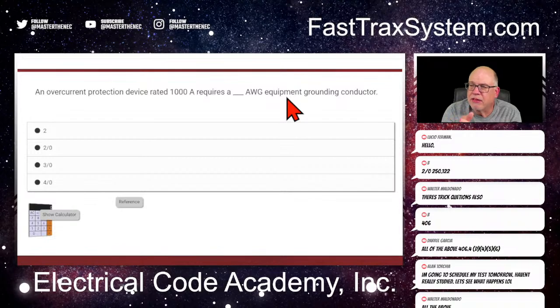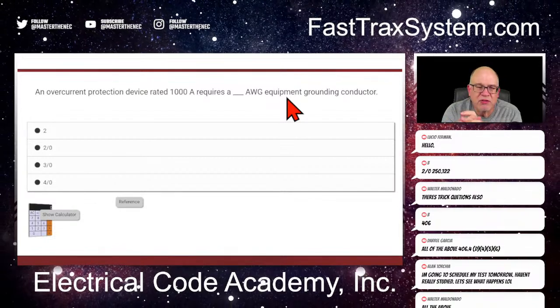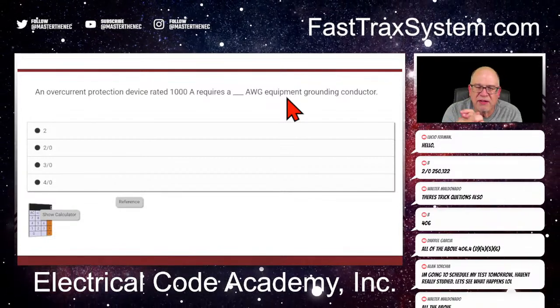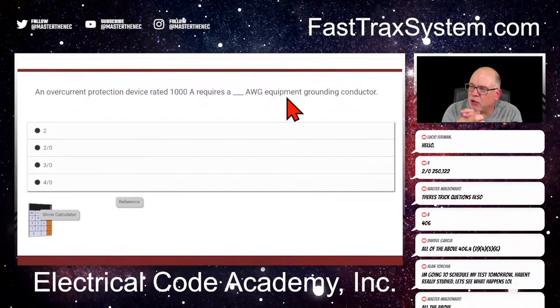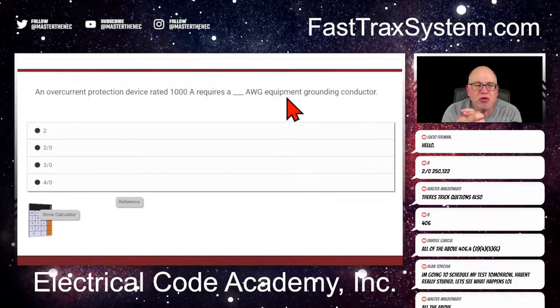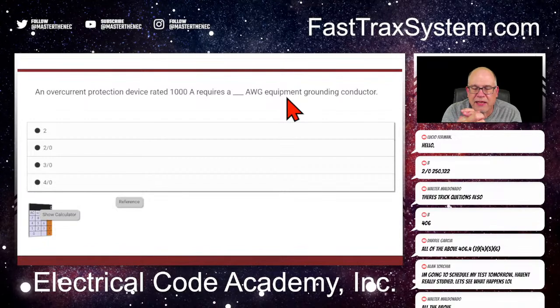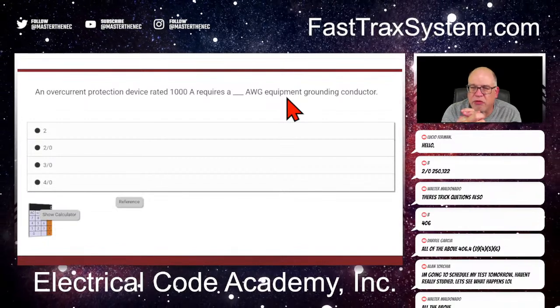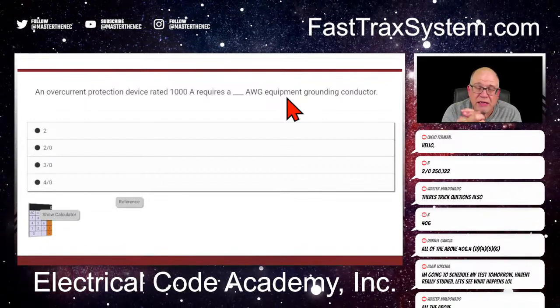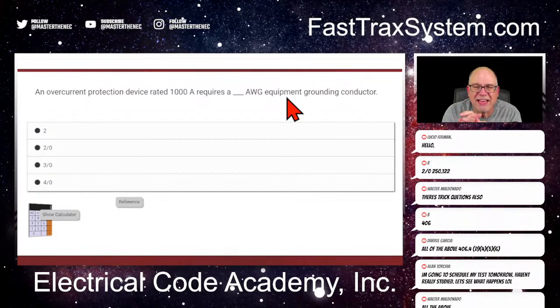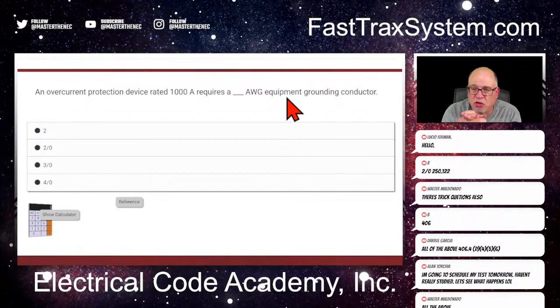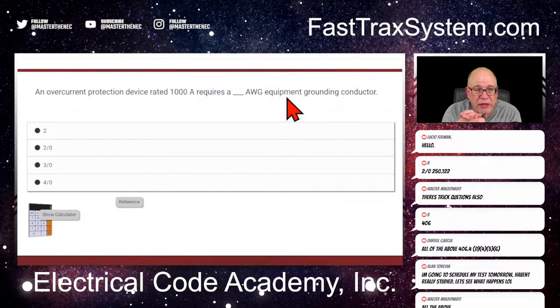All right, so first thing we notice in this question, B's giving us an answer here. The first thing we notice is that it's an equipment grounding conductor. You should know right off the bat that equipment grounding conductors are sized based on the overcurrent protected device. The overcurrent protected device here is 1,000 amps.